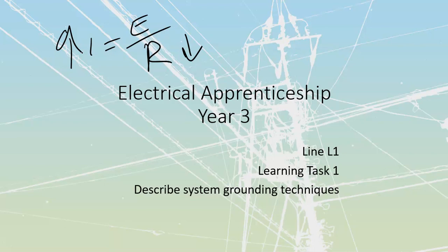The next system we're going to talk about is impedance, which is where we're going to once again have a system with a neutral, but then we're going to take that neutral and connect it to ground, not directly with a conductor, but rather through a very large impedance, or opposition to current flow. Sometimes the impedance can be resistive, other times it's going to be inductive. But because it is going to have some sort of a choke on the system, whether resistive or inductive, there's going to be a small amount of current that's going to flow, and it's not necessarily going to be enough to trip out our breakers.